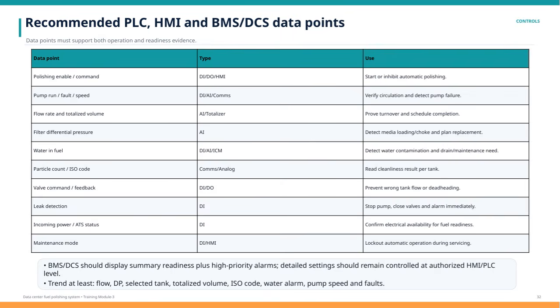At the BMS or DCS level, summary readiness status and high-priority alarms should be displayed for quick situational awareness, but detailed settings must be kept accessible only to authorized personnel via the HMI or PLC. Trend data for key parameters like flow, differential pressure, specific tank statuses, totalized volume, cleanliness codes, water alarms, pump speed, and faults should be recorded to provide clear insights into system performance over time. This comprehensive monitoring and control approach supports both operational reliability and regulatory compliance.